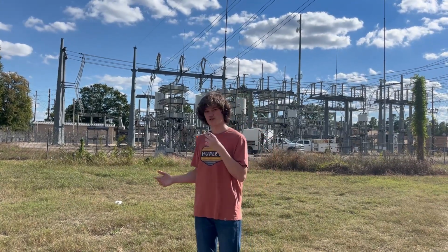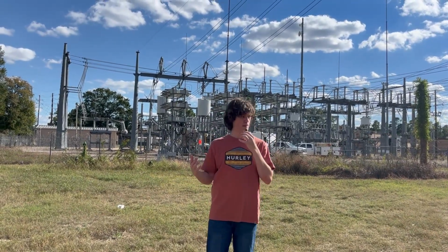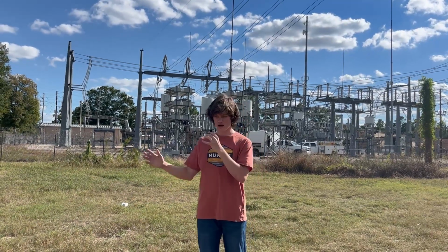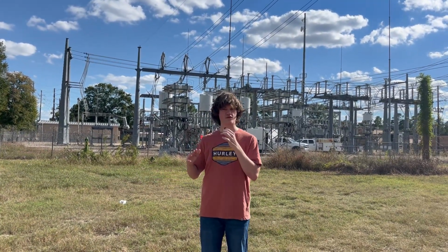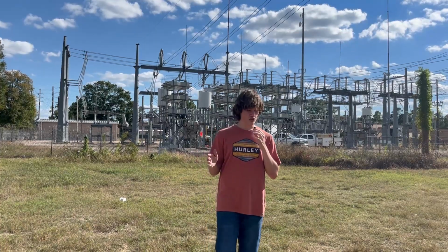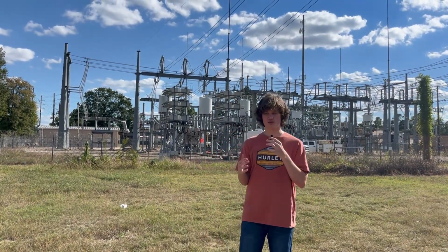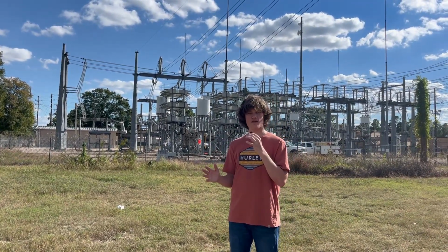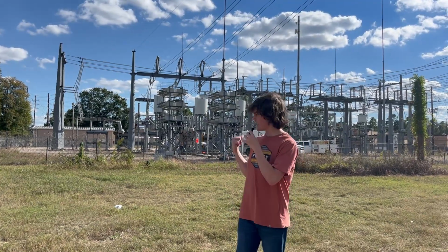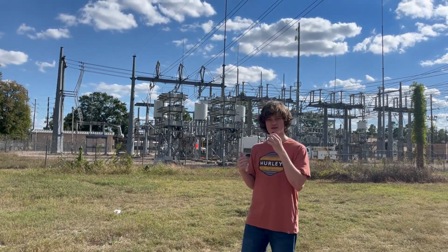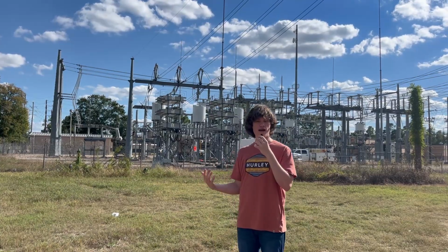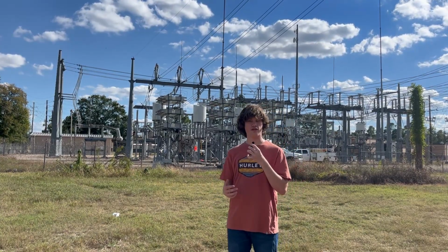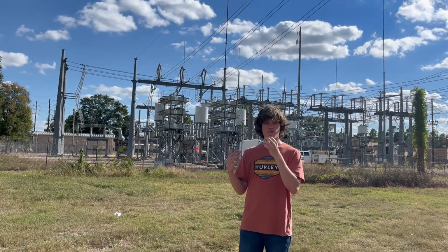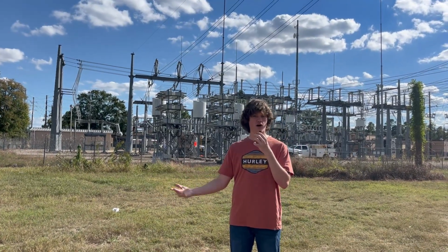The same thing happens when you connect capacitive loads, but in the opposite direction, meaning your current wave is front shifted. Since these two are opposite each other, you can use them to counteract each other and get your power factor closer to one, which is exactly what grid operators do. Behind me are rows of shunt capacitors used by grid operators to regulate the grid and keep the power factor as close to one as possible.